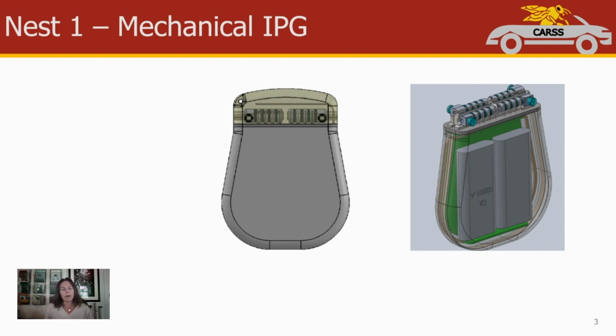The hermetic enclosure will be made primarily of titanium that will be laser welded together to form the hermetic barrier. The titanium grade is selected to facilitate the charging without overheating the IPG during charging once implanted. The titanium case can also be marked with any pertinent labeling and identification that is desired or required by regulatory authorities. As for interfacing with the IPG, the header has 4 lead access points with 4 ball seal IS4 style contacts, or, like I said earlier, 2 8-contact leads. Additionally, there are 4 sets of set screws to secure the leads into the header. Additionally, Nest 1 includes the external charger that accompanies the IPG.